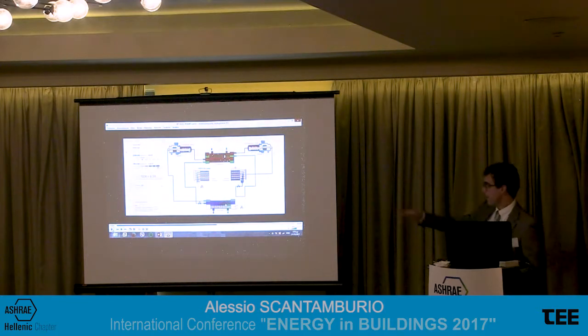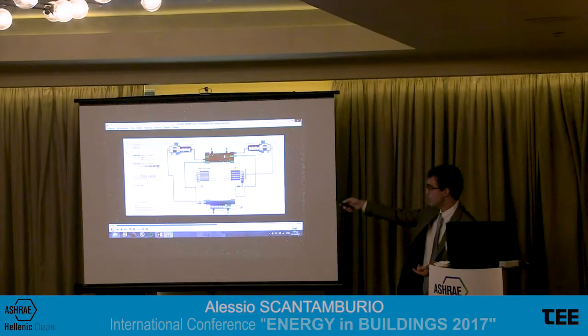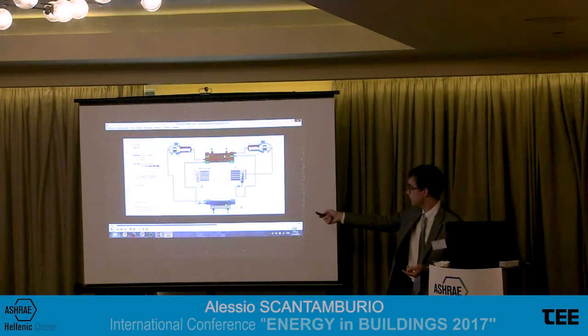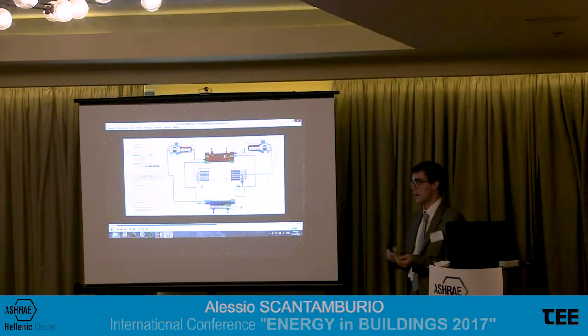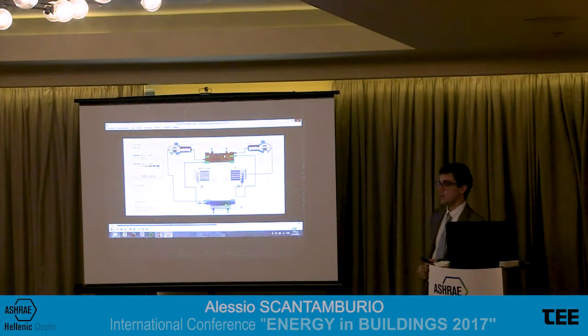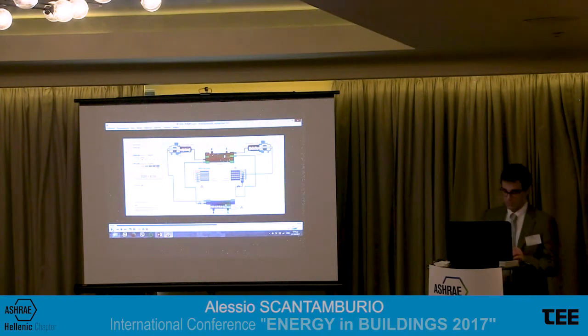Of course, the unit is able to manage all the combinations of load, because this auxiliary exchanger can work either as an evaporator or as a condenser. So we don't have the limit of a chiller with total heat recovery in terms of combining the requests of the building.